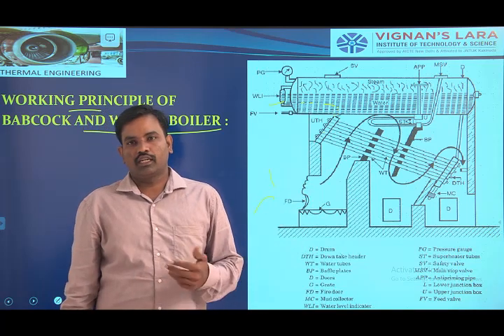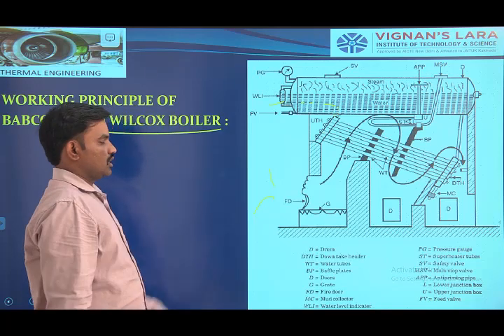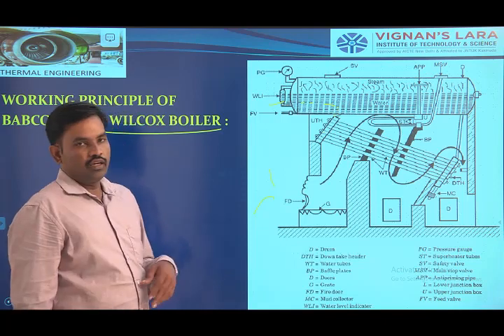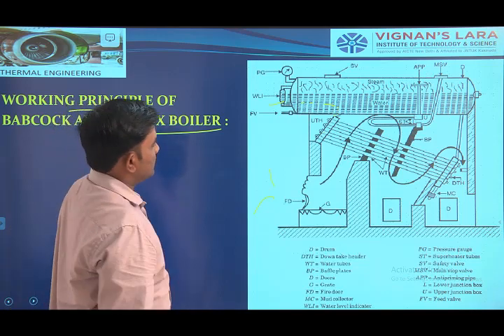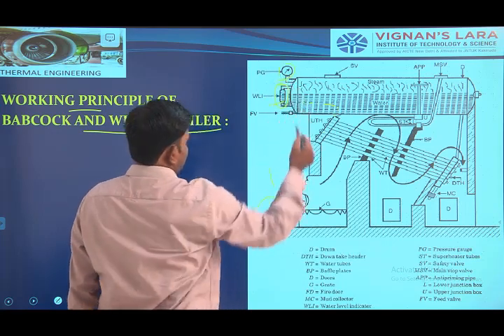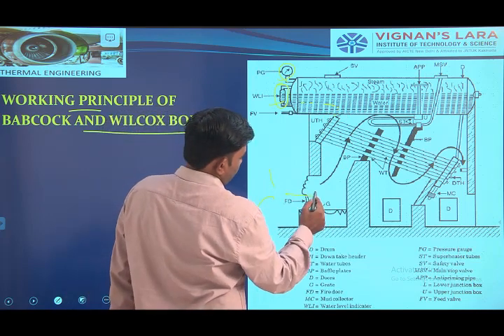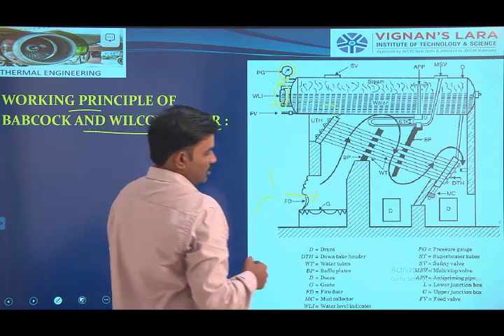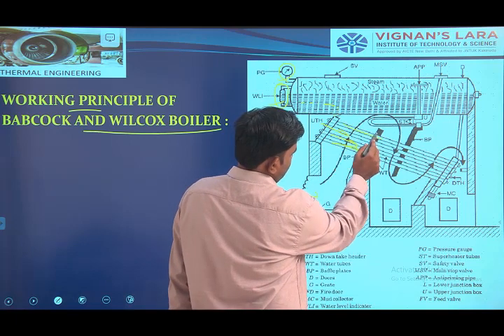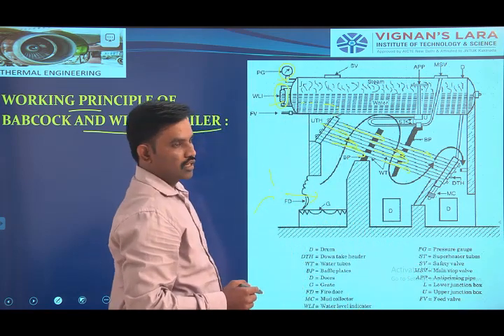It is a water tube boiler, natural circulation type. The hot flue gases are generated outside the furnace — that means it is an externally fired boiler. This type of boiler is also used in medium pressure applications. See the boiler mountings: this is the water level indicator, this is the pressure gauge, this is the boiler drum to accommodate the water. These are the different inclined tubes, arranged in order to flow the water from the upper header to the lower header.